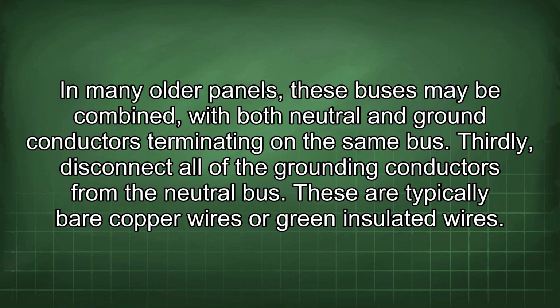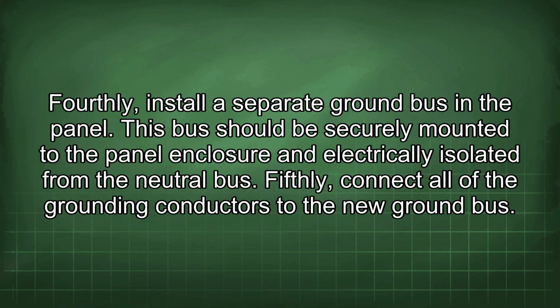Thirdly, disconnect all of the grounding conductors from the neutral bus. These are typically bare copper wires or green insulated wires. Fourthly, install a separate ground bus in the panel. This bus should be securely mounted to the panel enclosure and electrically isolated from the neutral bus. Fifthly, connect all of the grounding conductors to the new ground bus.